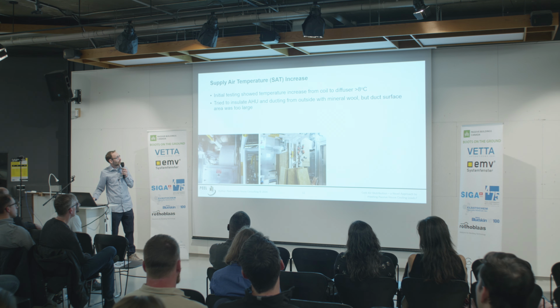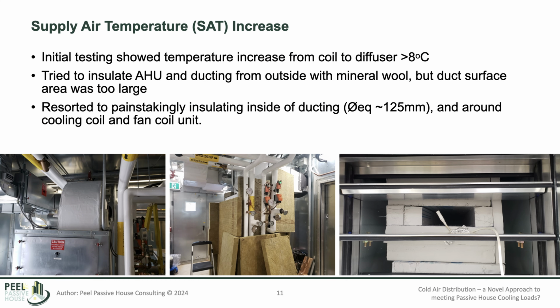Well, that was basically because there's too much surface area. So a colleague at U of T and I painstakingly cut pieces of insulation to make a duct within a duct, equivalent to about a 5-inch duct within the duct. When I did that, towards the end of the experiments, I got down to less than 2 degrees coming out of the diffuser—actually colder than what we were targeting.